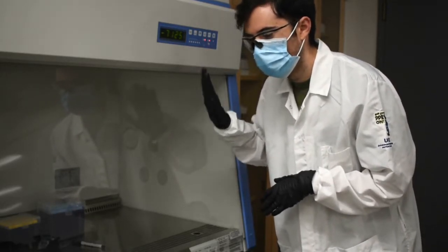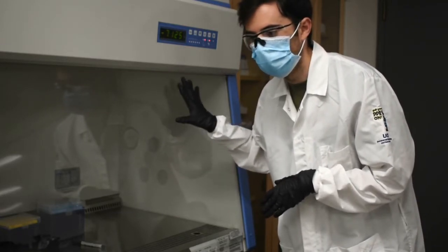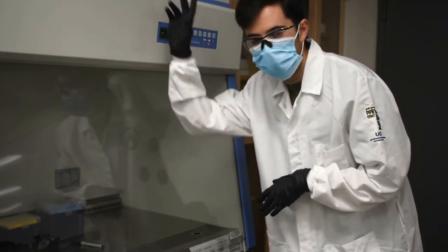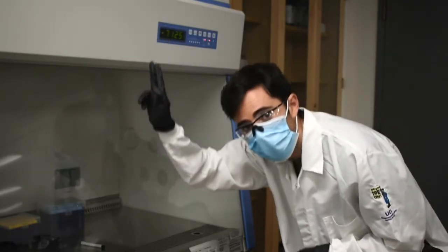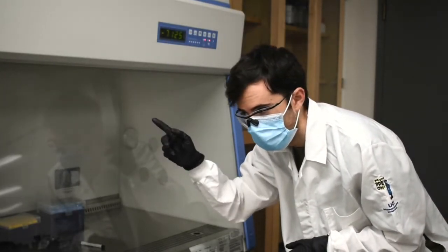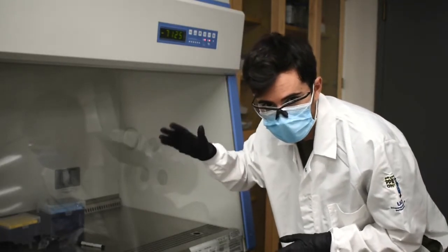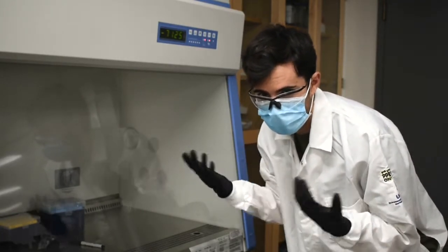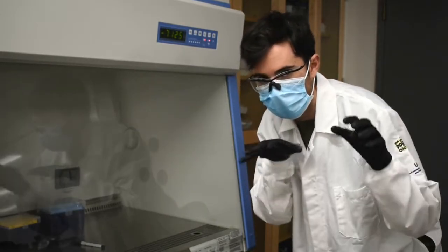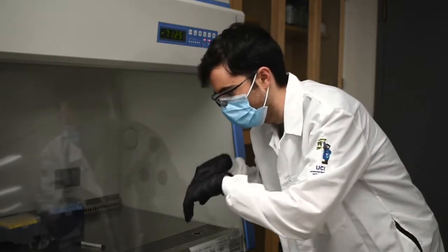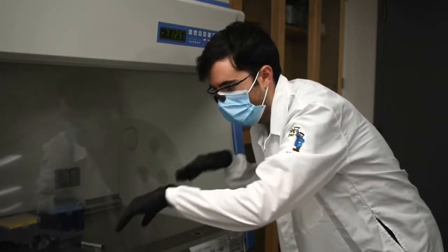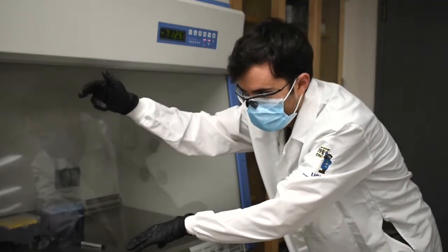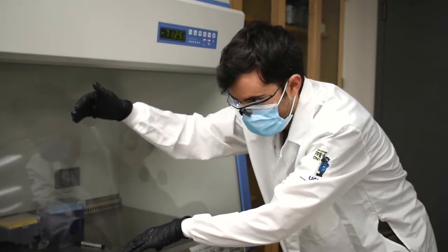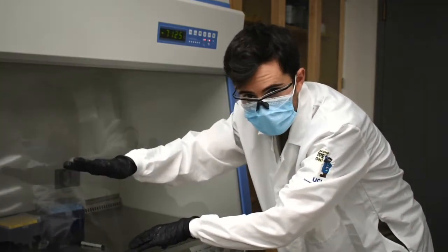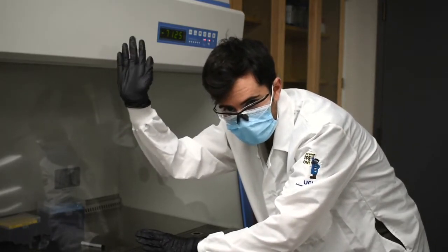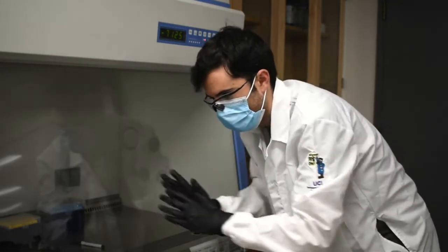And so, just briefly to talk to you guys about this before I open the hood, there are HEPA filters located at the top of the Biosafety Cabinets. And what's nice about it is you can have recirculation of air and not have to worry about any sort of pathogens, as I said earlier. And so what happens is air from the system, so the surrounding background, will come into these front vents, the grills right here, as well as some of the recirculated air from HEPA filters, as well as working in the system, will go into the vents up to the back, and it will go through the HEPA filters to then get purified and allow us to have a clean space.